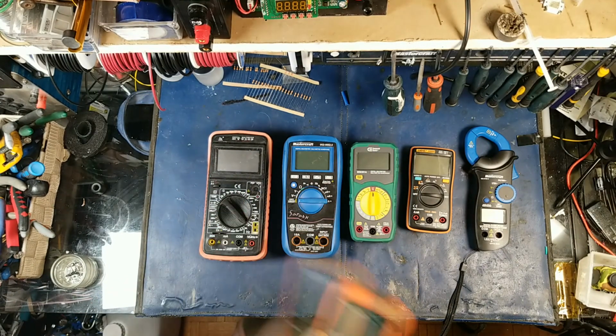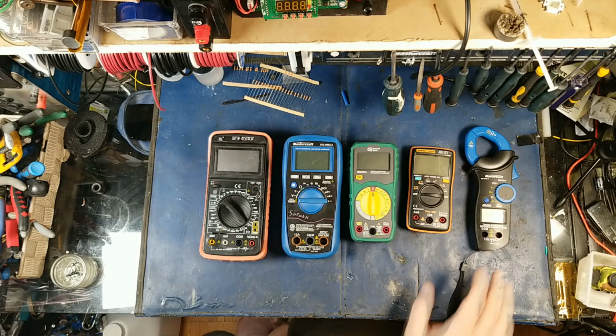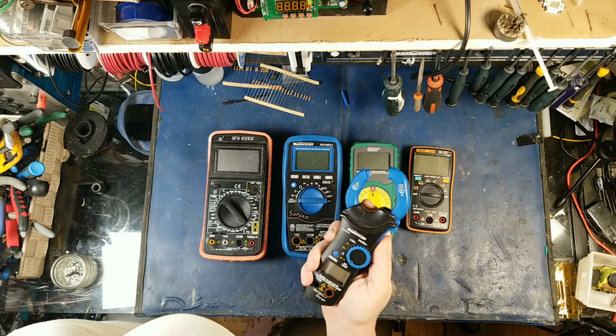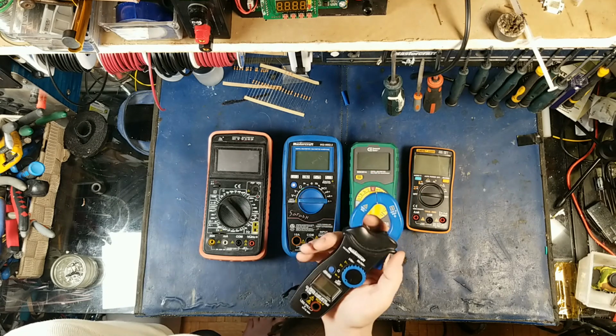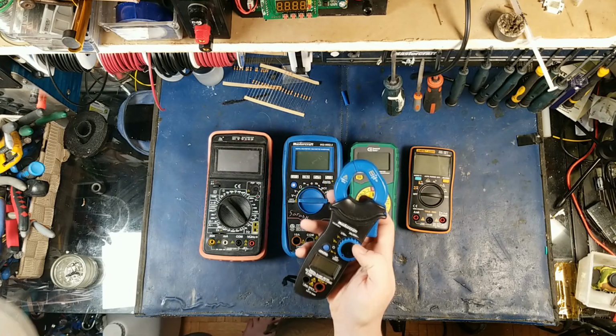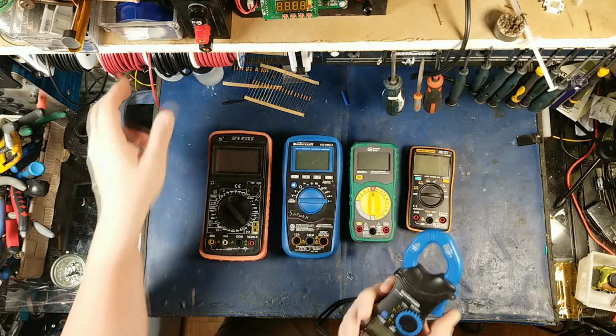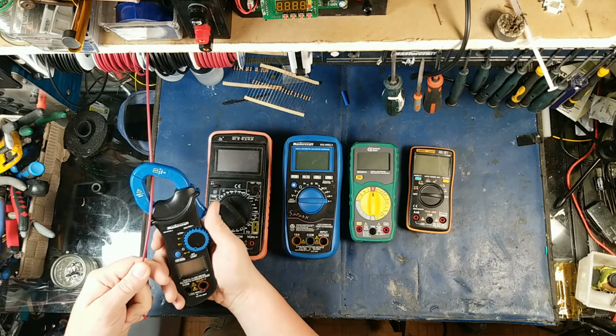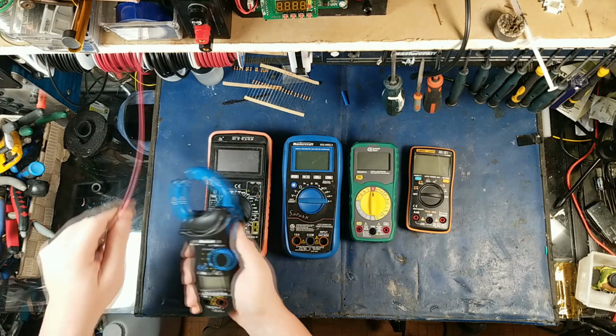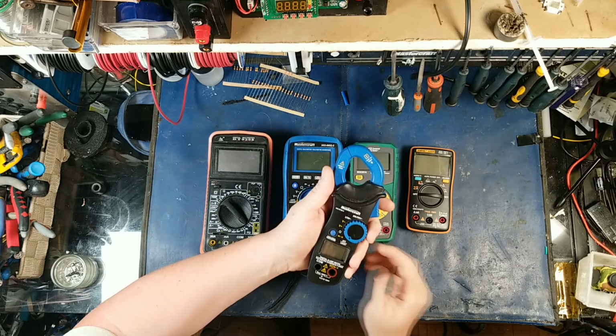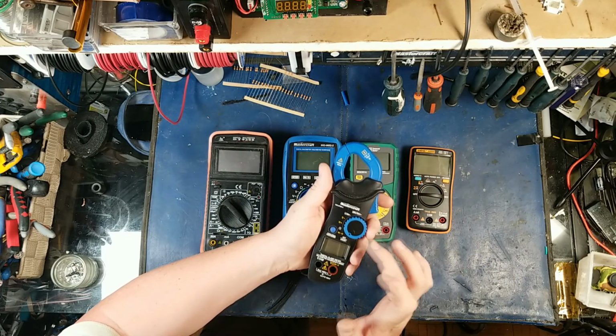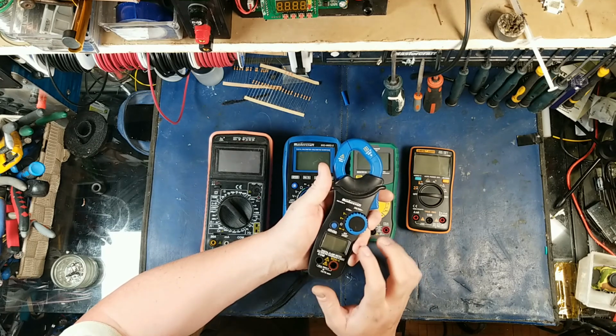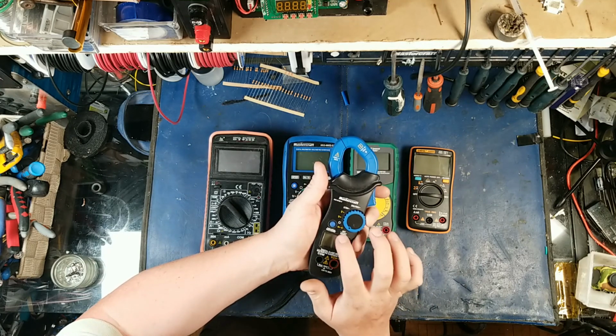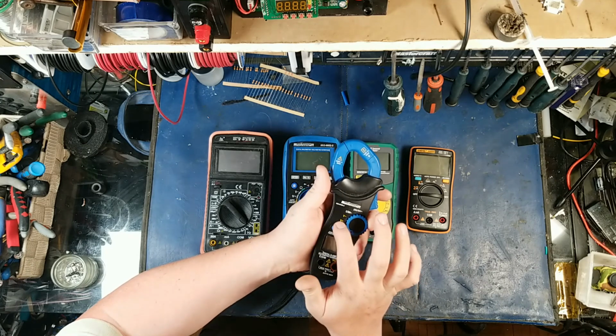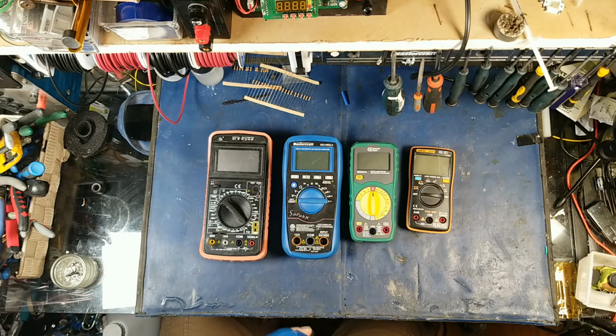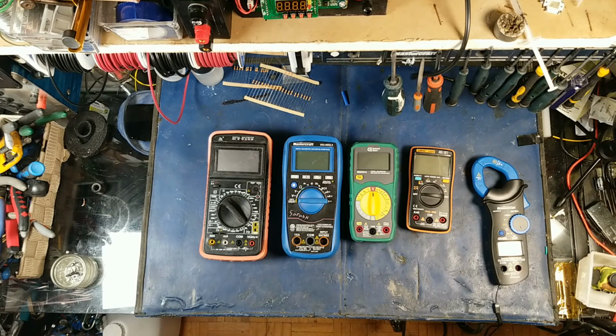So we can put these guys aside now. The more common ones you'll end up using will be like this. This is just a cheapy clamp meter. These clamp meters are handy because you can test, on this one, 200 to 600 amps just by clamping it over one leg of a circuit. You typically clamp this onto the hot, and it will measure the electromagnetic field being induced off the cabling to show you how much current's passing through it. It's kind of cool. But this one also, you can connect probes to it and get your continuity, resistance, and your AC and DC.